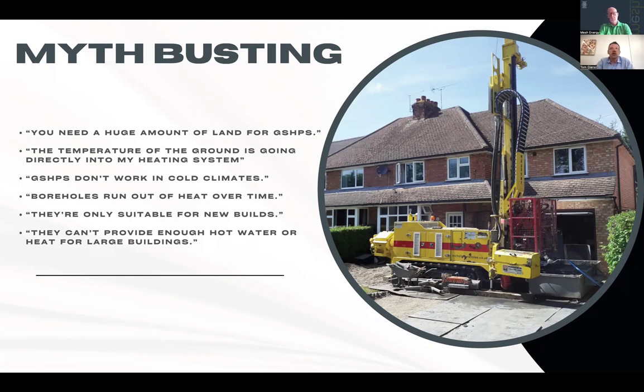If you are designing a system with heating for the house, hot water, and an outdoor swimming pool, you will extract heat during the winter for the heating and hot water. Then in the summer the boreholes are not resting, because you then have quite a heavy demand to heat your outdoor swimming pool. So the running hours of the system are very important, because if you switch on your pool heating, the boreholes don't have the rest time to recover and recharge. You are then extracting too much heat, and that's when they lose their efficiency. So the running hours have to be taken into consideration if you are heating the pool.